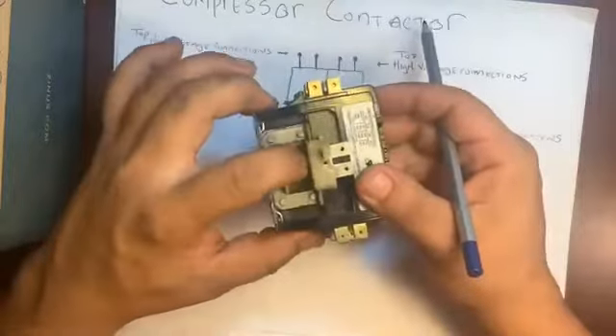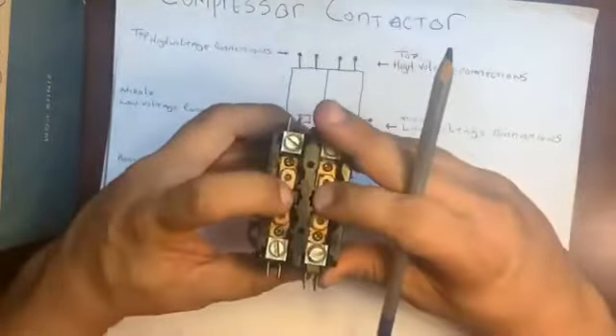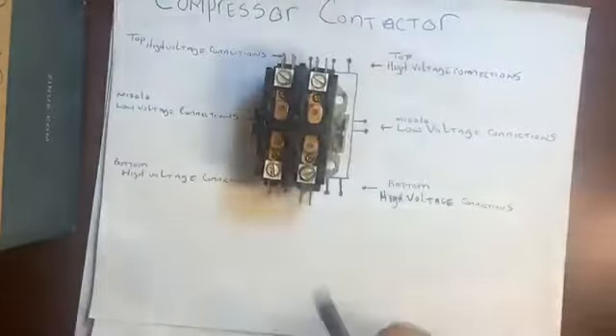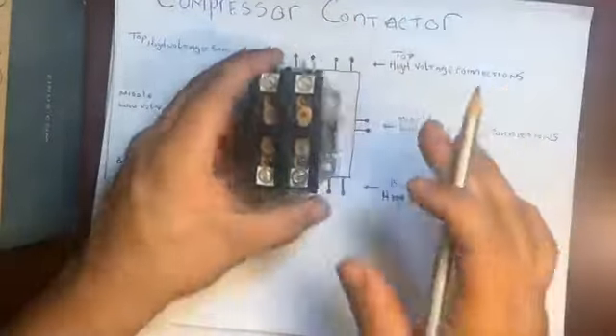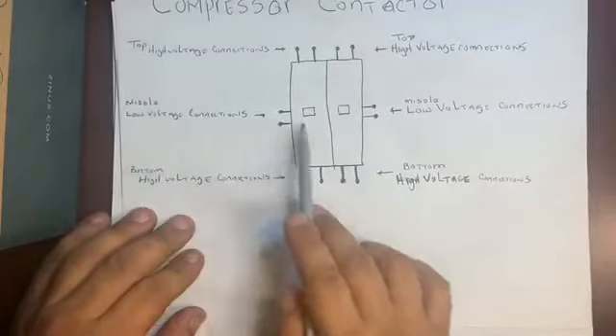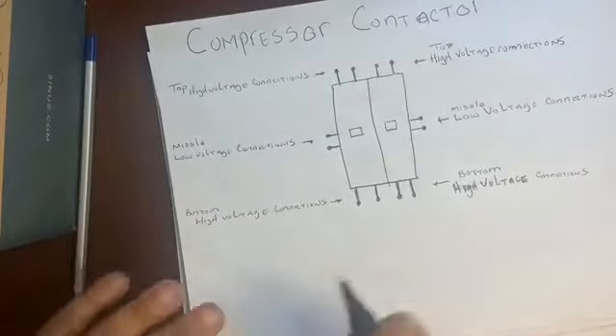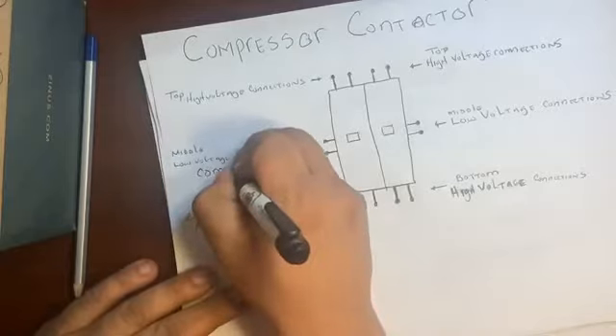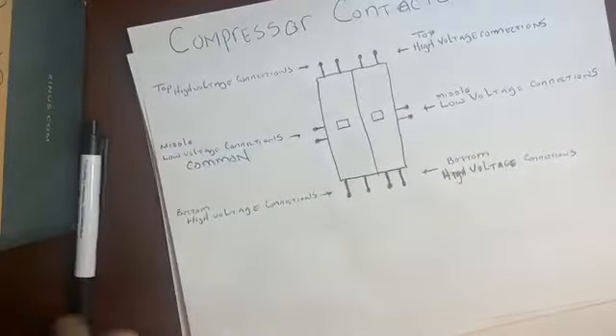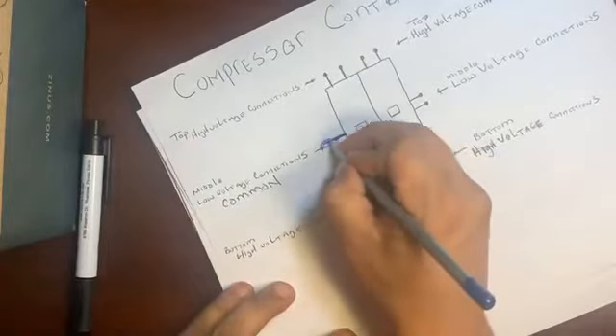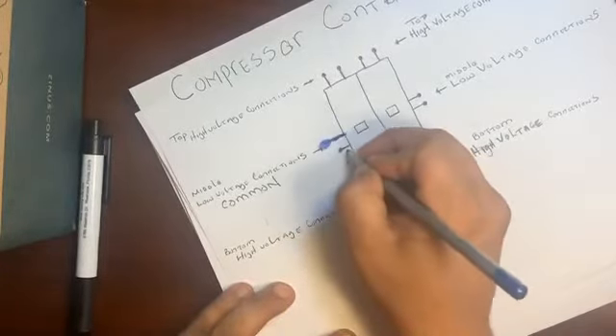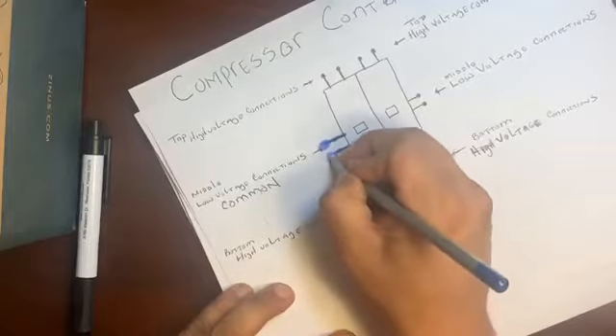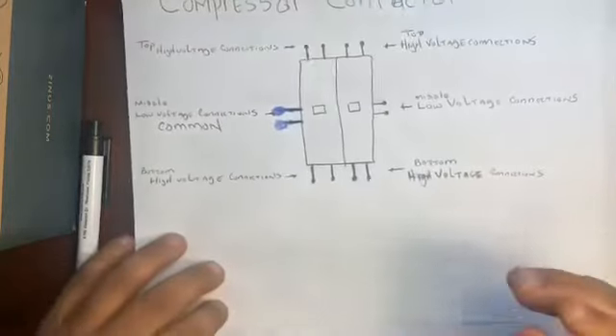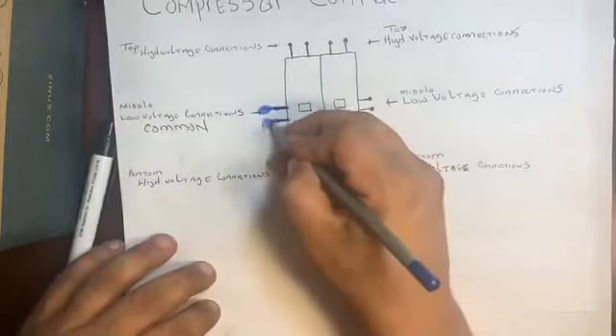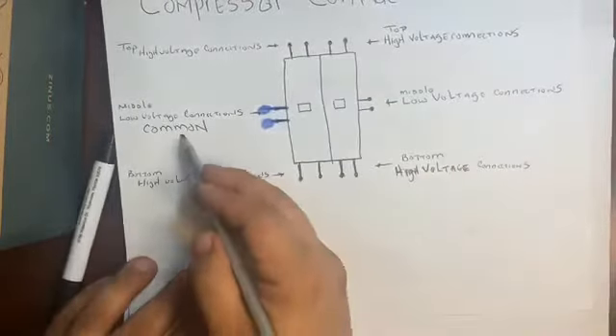The reason this works is there's a coil on the bottom. And once it's energized, it pulls the plunger in and completes the connection. This is your compressor contactor. Again, just like any other relay, find your low voltage connections and designate one low voltage common. And what color is low voltage common every time? Blue. For the purpose of this diagram, it's gonna be blue. In the field, sometimes there is a different color, sometimes it's brown, depends on the machine. For now, we focus on blue. Blue is the low voltage common.